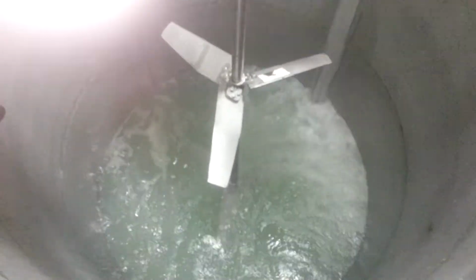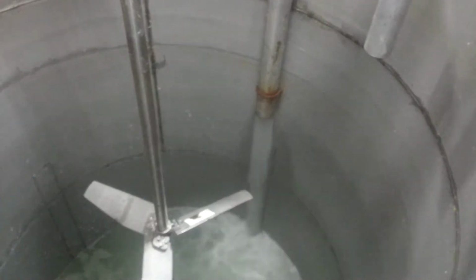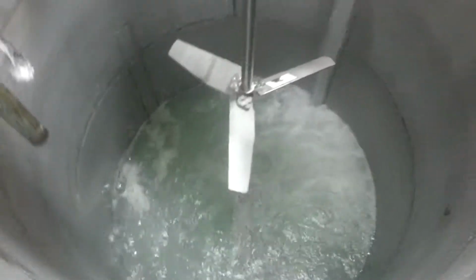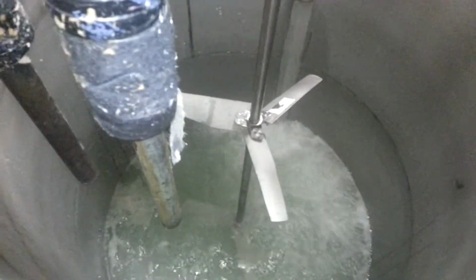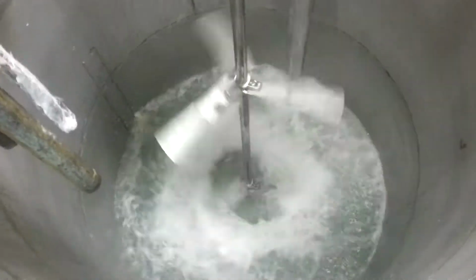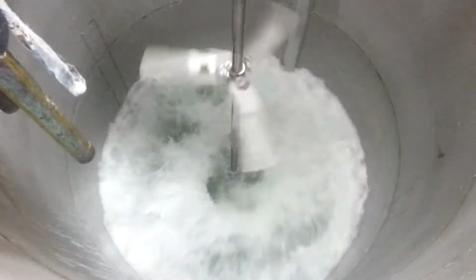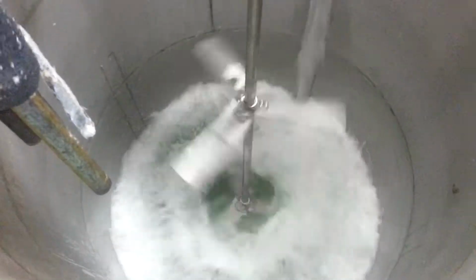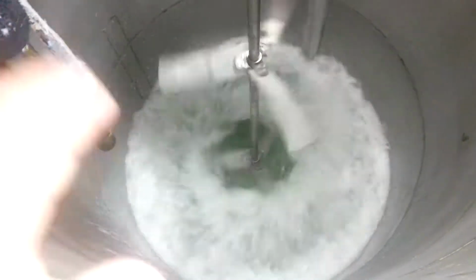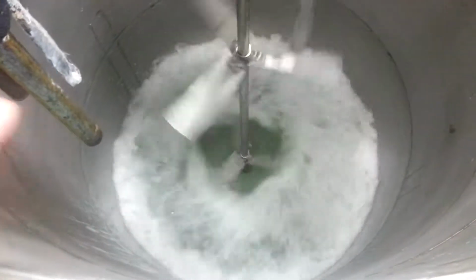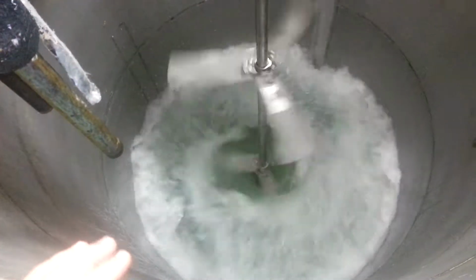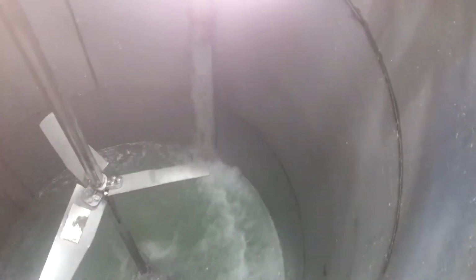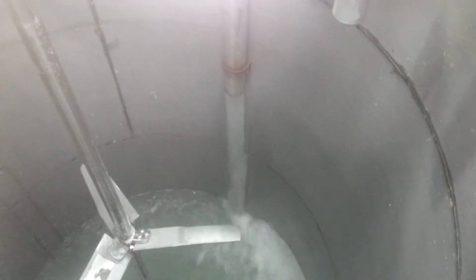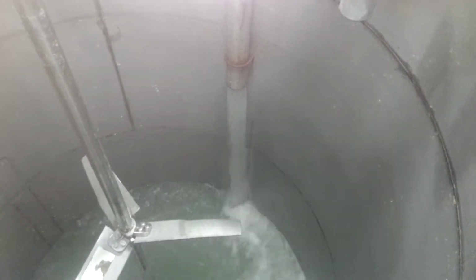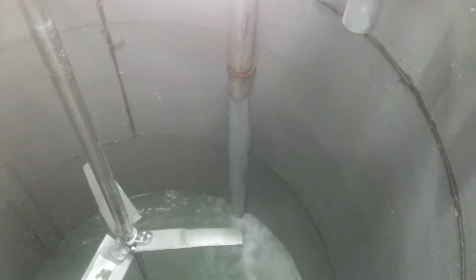Here's the tank. The tank diameter is about 12 feet, and you can see the return liquid in our flow loop. We've got an impeller in the tank, everything stirred. And we like to keep the level of the tank at least a quarter to a third. The pump that we're using requires a certain hydrostatic pressure, or head, that pushes the liquid into the pump, preventing something called cavitation. Just to give you an idea, that flow is through about a 4-inch pipe, and that's about 50 to 100 gallons per minute going through there.